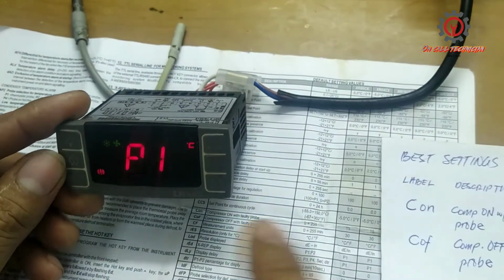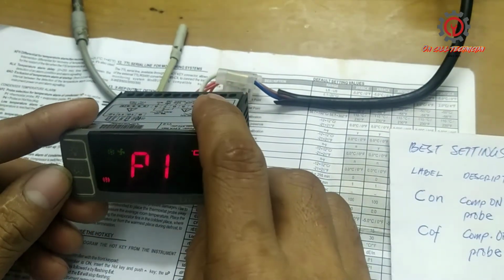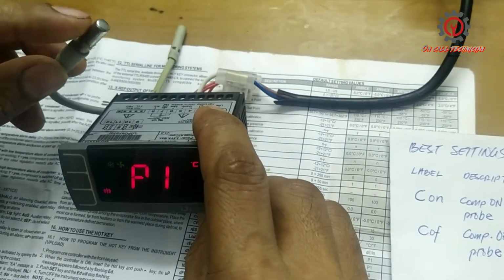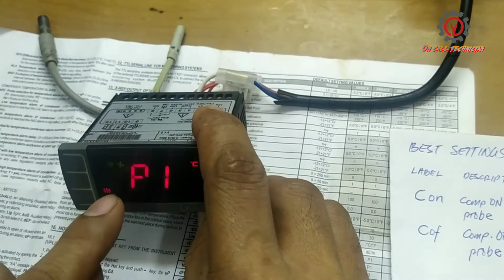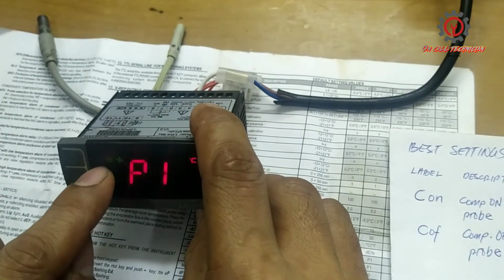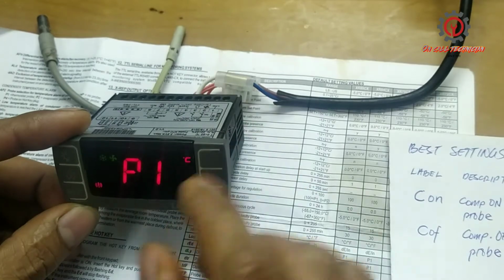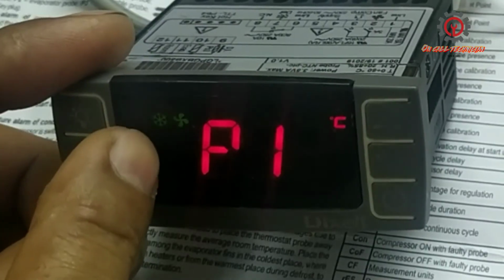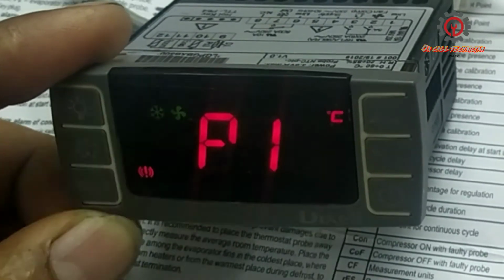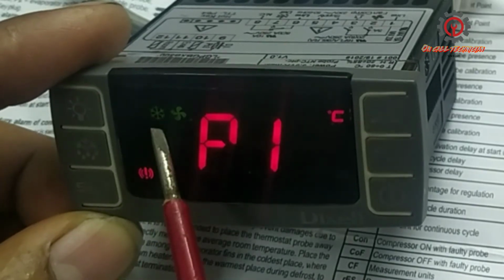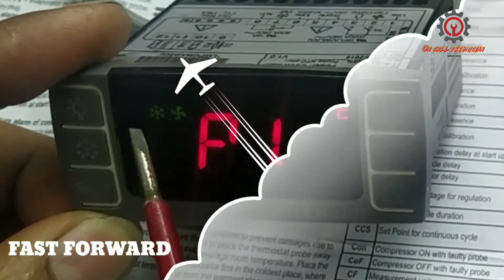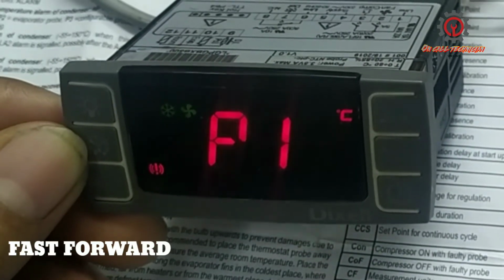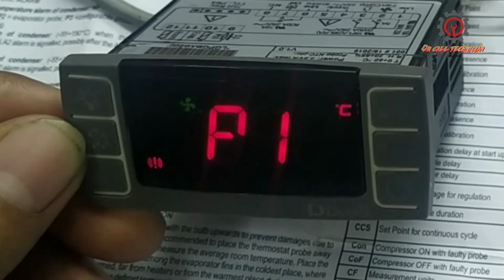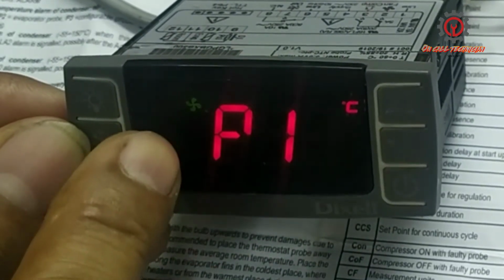And take a look, we have a sensor problem, and this is our thermostat, but still the compressor is on. And let's wait for the 1 minute. After 1 minute, let's see if the symbol here for the compressor on will turn off. Okay guys, it turned off.